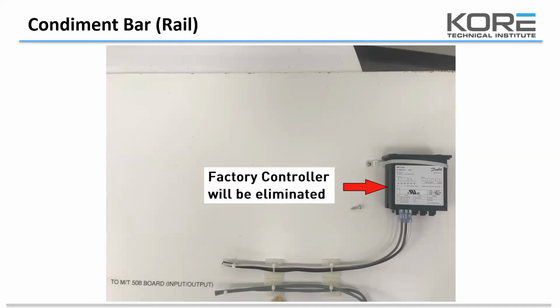Basically, it's the same as the kitchen and the freezer. You'll see here that the newer condiment rails or bars have the Danfoss Dixell style controller. Usually you'll see that it has 3 wires. You've got a brown wire that is the load side to the compressor. The black wire is the power in. And the white wire is just additional to supply power to the Danfoss controller to operate.